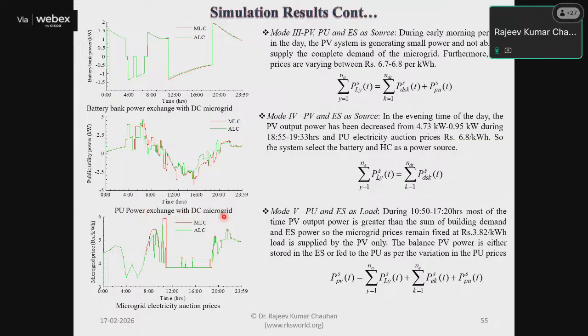Then PU power exchange with the DC microgrid, where PU is public utility power exchange. We can see manual control sometimes shows power exchange, but in automatic control, when prices are high—during the interval from 10, 11 to 17—most of the time the PV is greater than the sum of building demand and ES power. So the microgrid price remains fixed at 3.82, and therefore the load is supplied by PV only, with balance PV power either stored in energy storage or fed to the grid, as shown here. Sometimes it feeds the grid, sometimes it consumes internally.